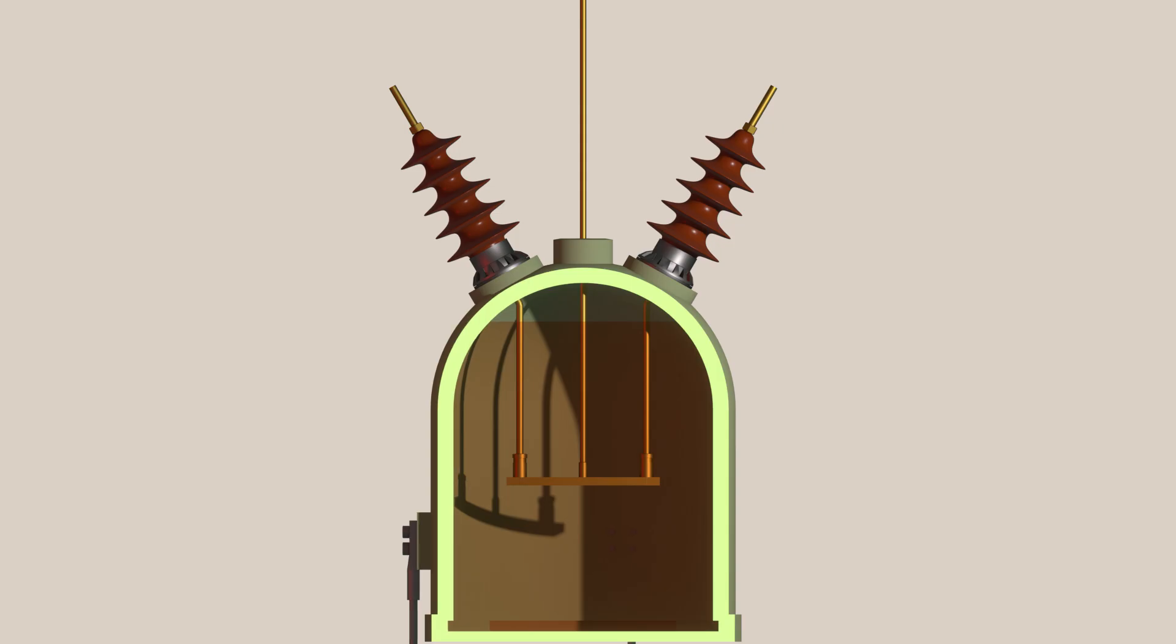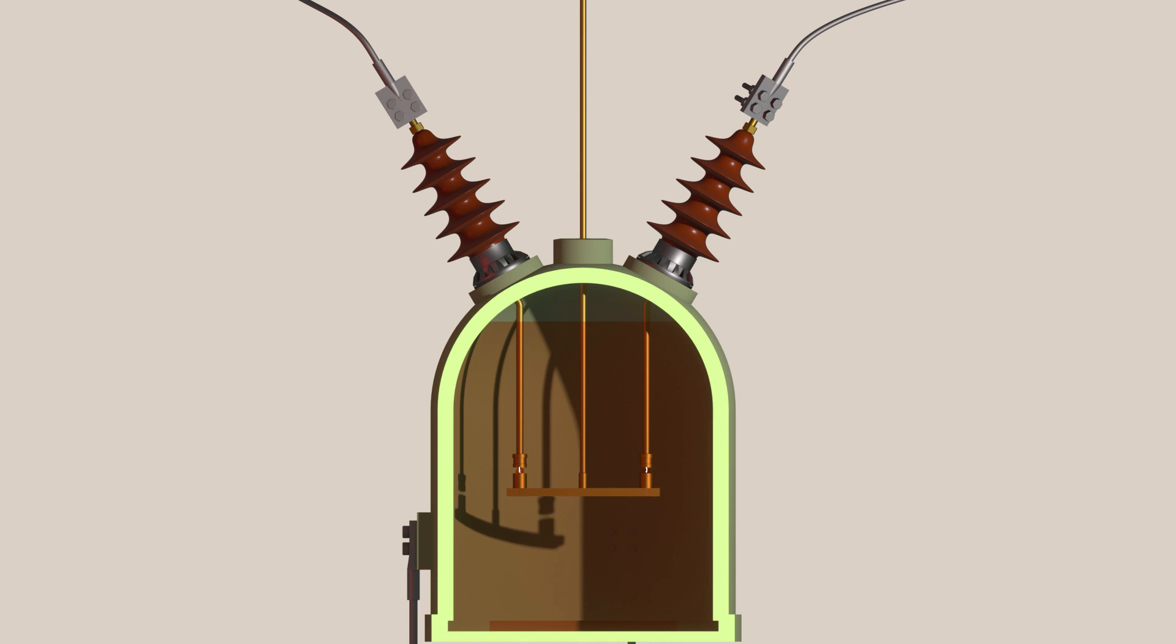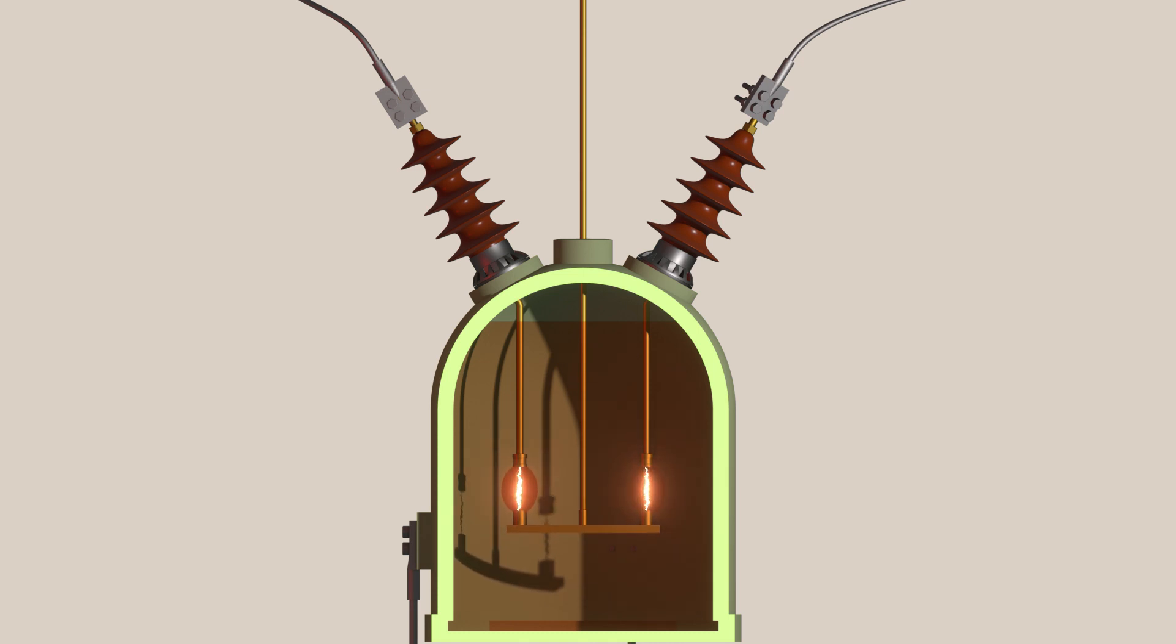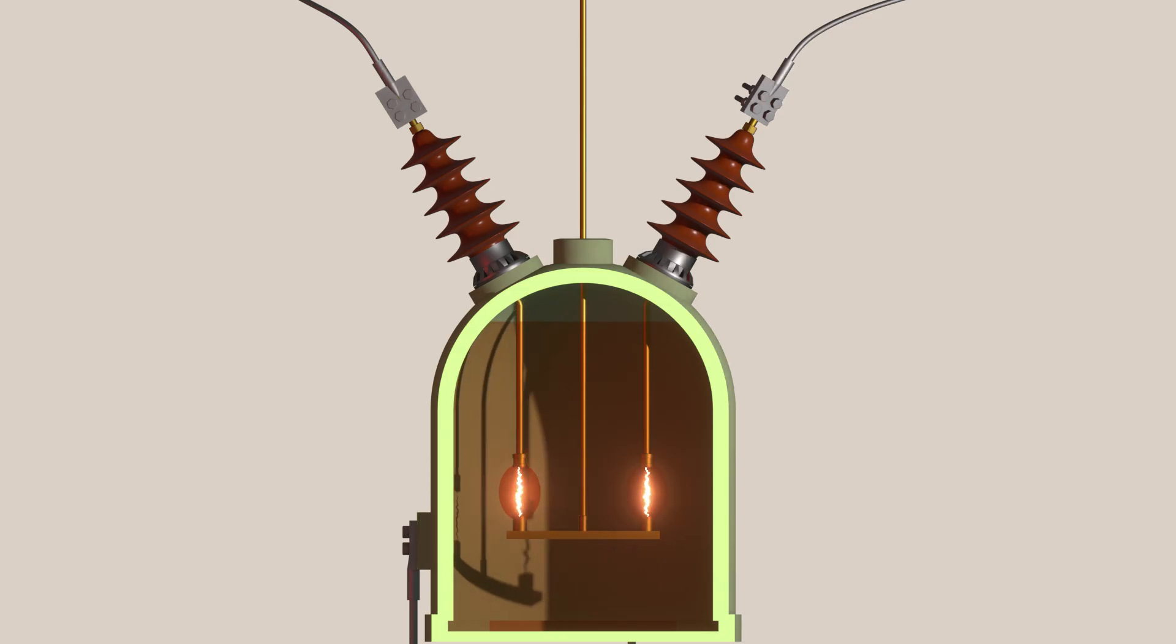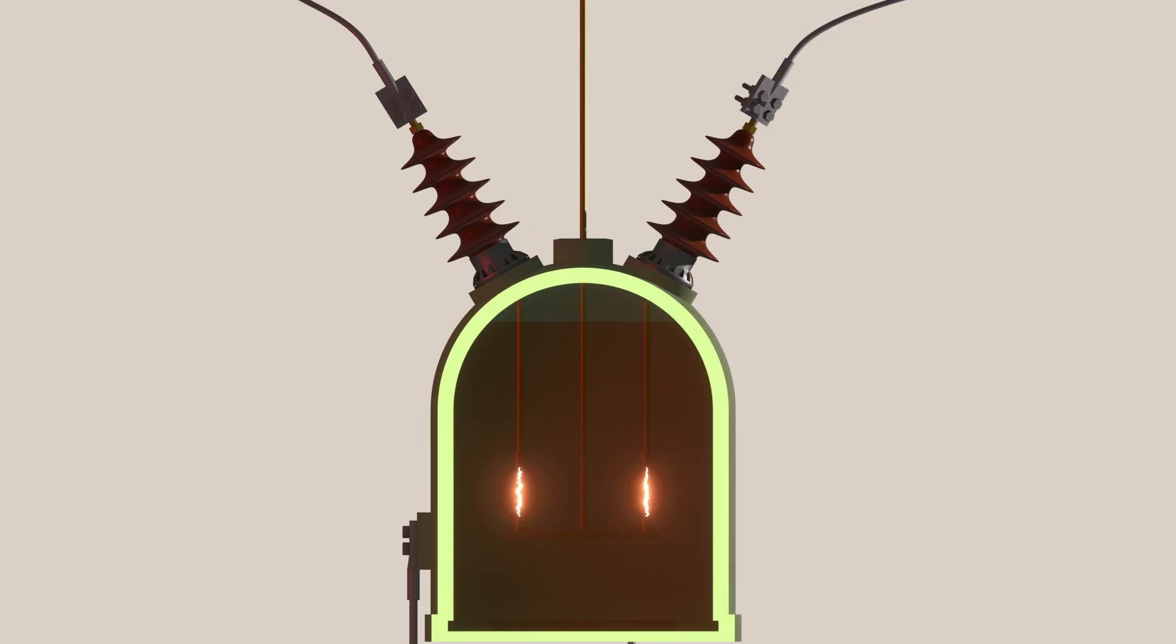Suppose the bushing studs are connected to the external circuit. When the moving contacts go down due to the tie rod movement, an arc starts between the contacts during opening. This happens due to the high voltage gradient at the instant they separate. The temperature becomes very high at the arc spot.